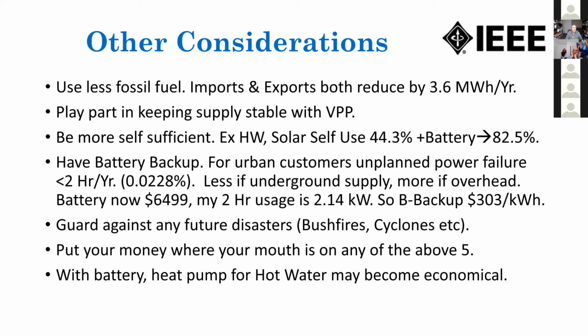You can have a battery backup. I've got underground power so power failures are very infrequent - with overhead power it's more frequent. For my system in South Australia, if I buy the battery now it's $6,500. The average power outage in Australia is about 2 hours, and my usage during that time is 2.14 kilowatts. So purely for battery backup, we'd be looking at $303 per kilowatt hour, when in North Queensland you can buy power for 26 cents per kilowatt hour.